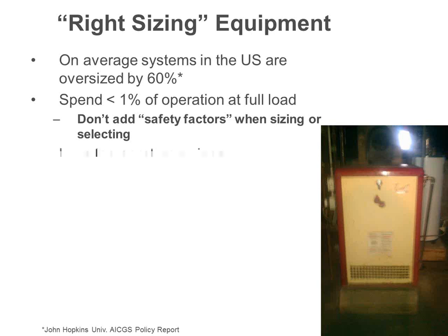Also, if you're the smart contractor and you don't go in and just read the tag, you will definitely have a smaller boiler. That means the first cost is less money. That means your bid should be a little less money than your competition that just went in and looked at the tag, because all he's doing is repeating the mistakes of the past. So you will have a lower first cost. It might take a little bit of explanation. But the easiest way to talk to people is to say, hey, last year, classic, one of the coldest years around, was your boiler constantly running?